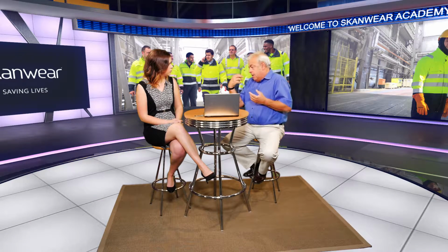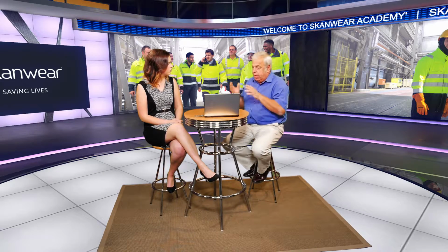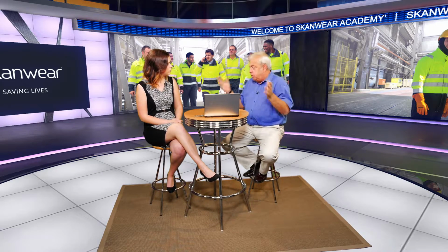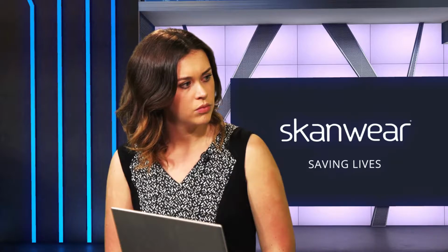And if they actually get airborne, the arc can form across the bridge. Finally, another cause, not so common, is that this equipment tends to get warm, and it attracts things like rats, mice, squirrels and snakes, and they crawl in. If they crawl across the bus bars and short it out, we've actually got an arc flash.